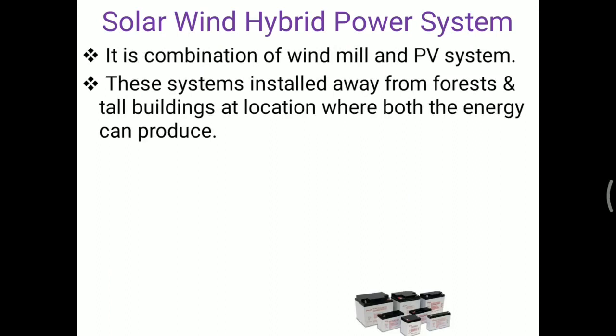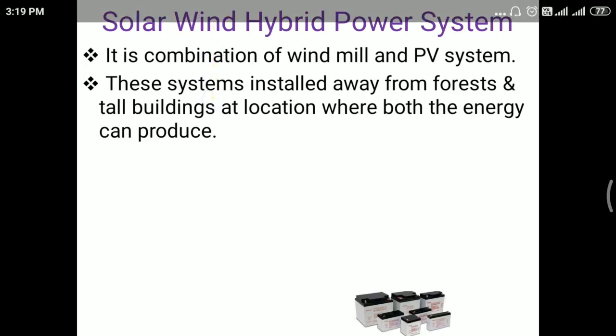This system is installed away from forests and tall buildings, at a location where both energy sources can be produced. If we install solar energy in a forest, due to shadow the production efficiency decreases. And if wind energy is installed near a city area, the air velocity is not maximum — the cutoff speed is very low and wind energy cannot be produced at maximum. So site selection is very important.